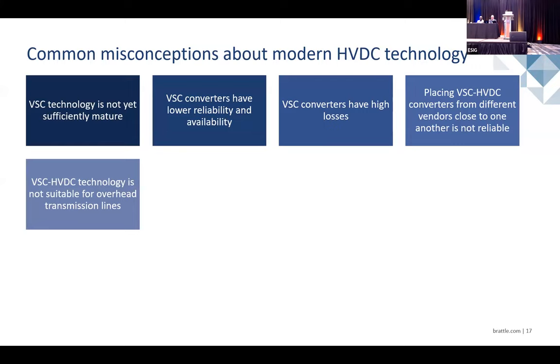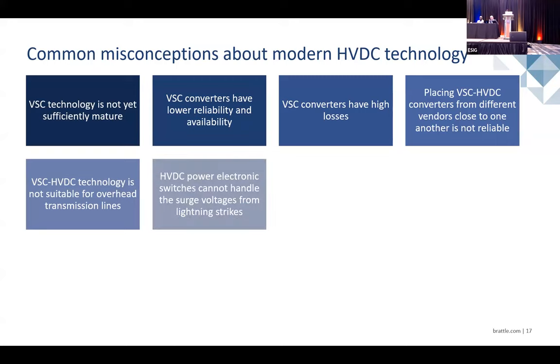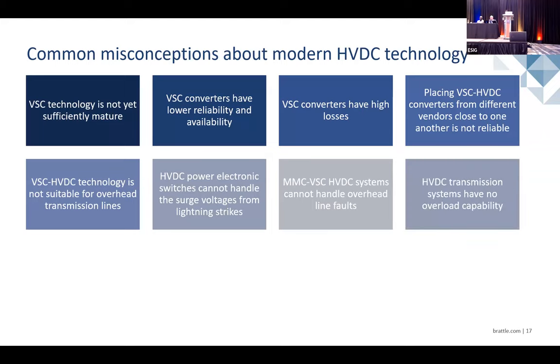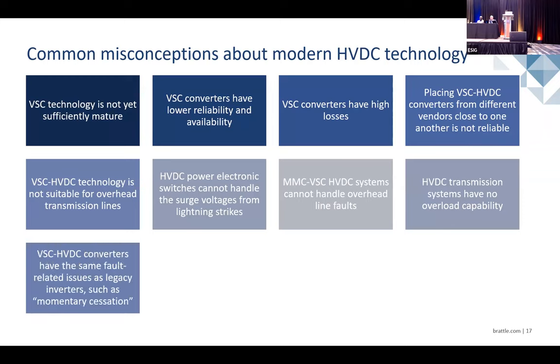Of course, there is a discussion going on about how fast or how slow that can be. The next one is about equipment withstanding lightning surges. Again, this is not a problem. Many converters have been designed and put into operation. As I said a few seconds ago, VSC is compatible with overhead lines and can handle temporary faults. If the client wants, he can also request an overload capability when buying the asset. Sometimes we get a free, inherent capability, and sometimes we have to take it into design considerations.